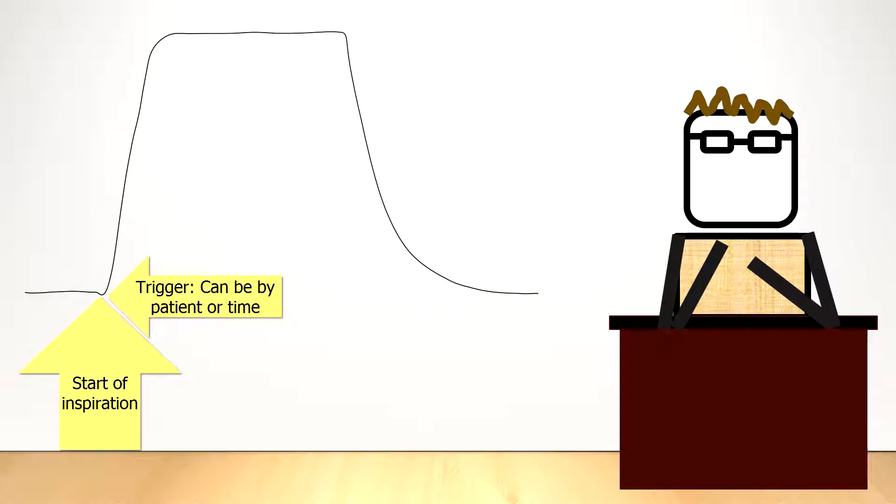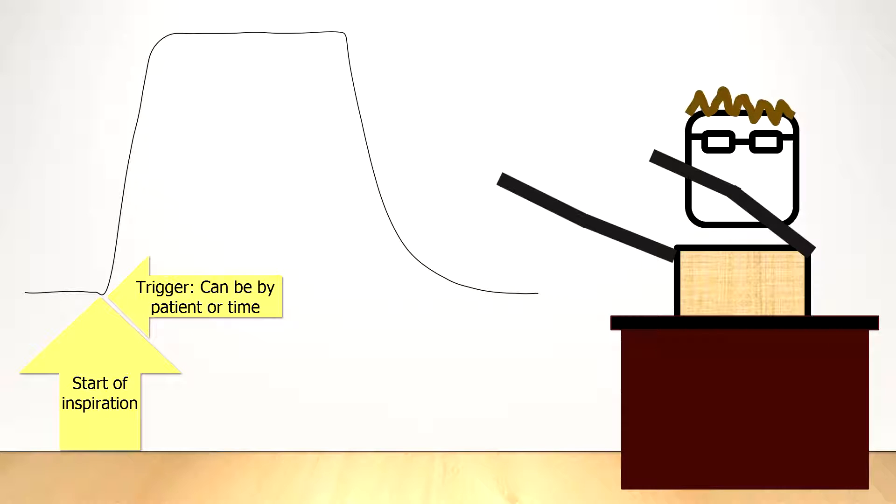The ventilator can also automatically deliver a breath if the patient doesn't trigger, or is unable to trigger, because of the effects of medications like neuromuscular blockade or sedation. The trigger in this case, then, is time. The ventilator measures the amount of time it has been since the last breath, and if it is beyond the limit, will initiate the next breath.